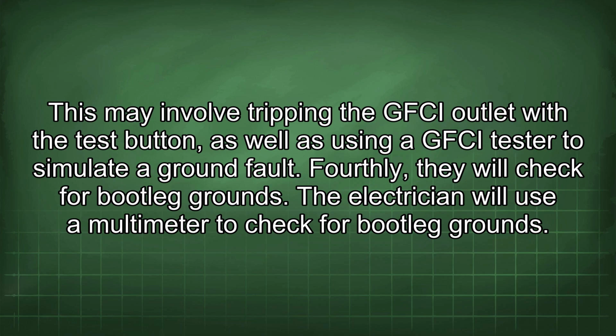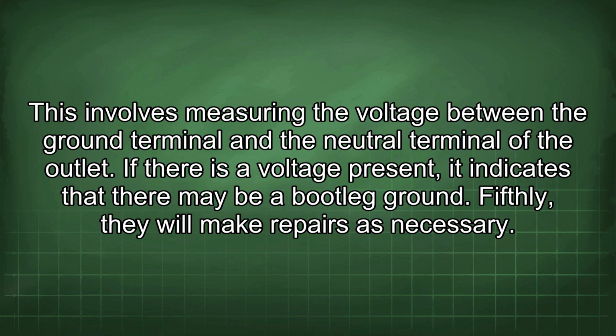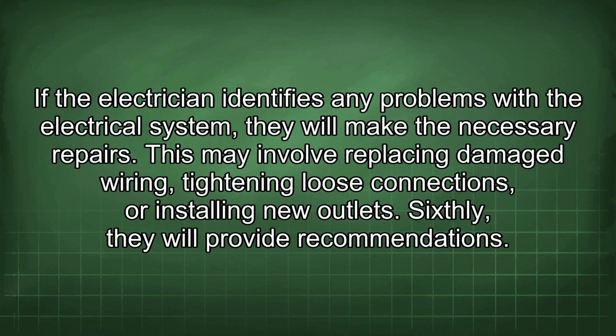The electrician will use a multimeter to check for bootleg grounds. This involves measuring the voltage between the ground terminal and the neutral terminal of the outlet. If there is a voltage present, it indicates that there may be a bootleg ground. Fifthly, they will make repairs as necessary. If the electrician identifies any problems with the electrical system, they will make the necessary repairs. This may involve replacing damaged wiring, tightening loose connections, or installing new outlets.